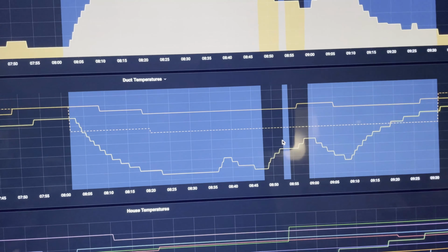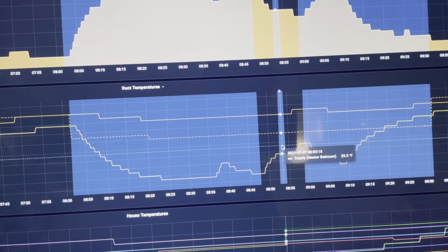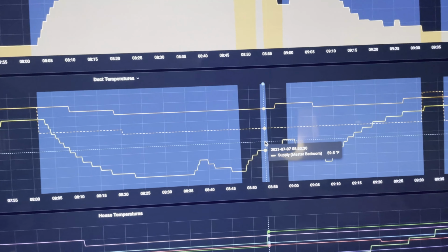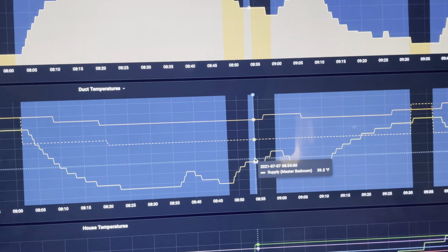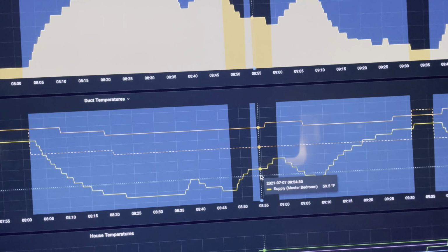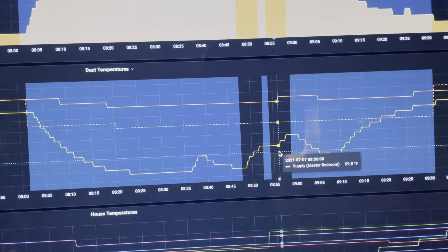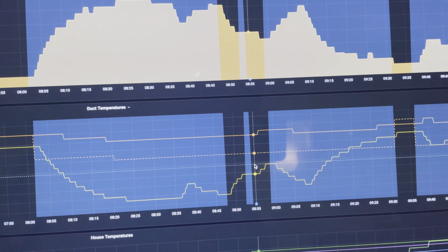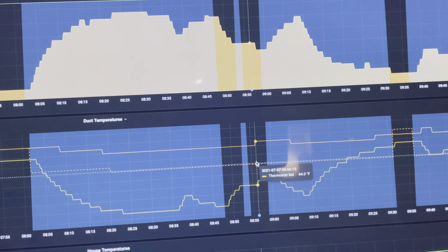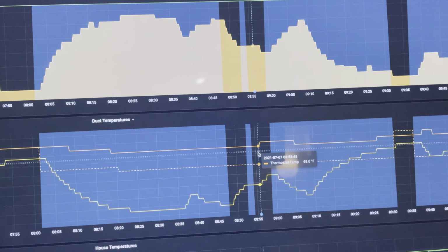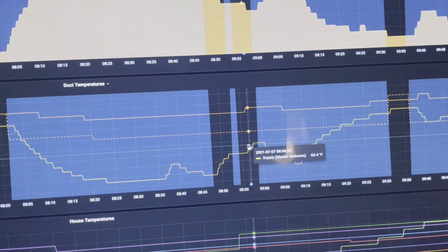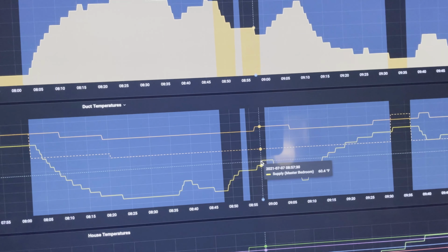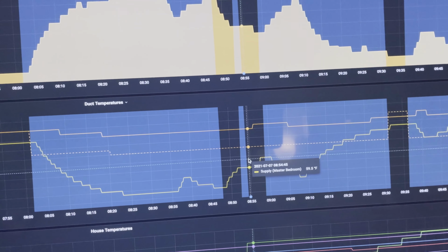So after we waited out the delay, it clicked back on. And at that point, we were having a conversation about how that works, and he disconnected the 24-volt wire to see what would happen. And so it kicked back off again and went into a delay. So this black background, while the set point is set below the indoor temperature, and you would expect it to cool, but it isn't calling for cooling, this is characteristic of the Nest going into that delay.